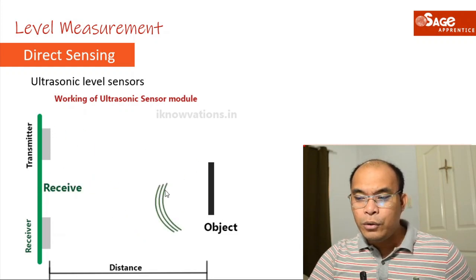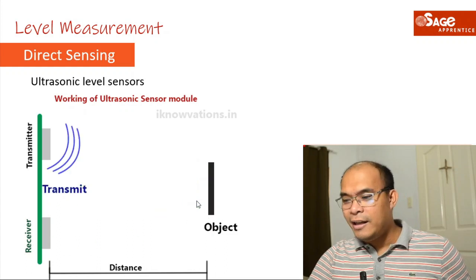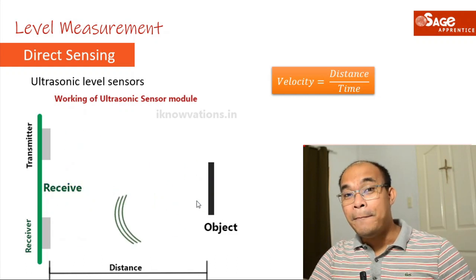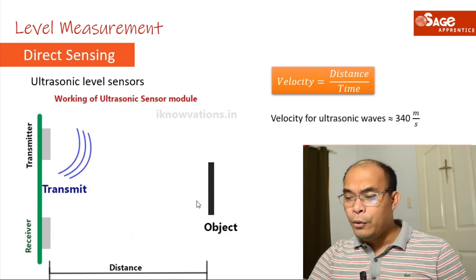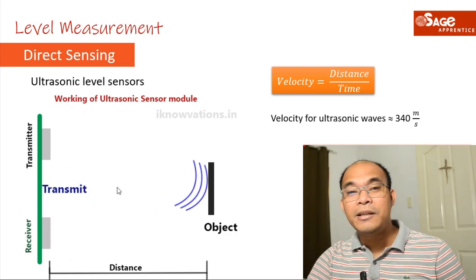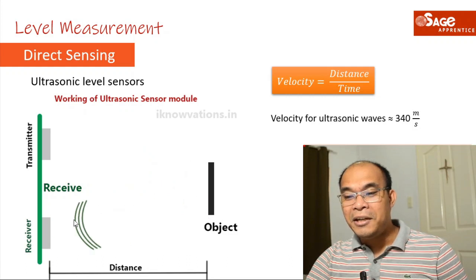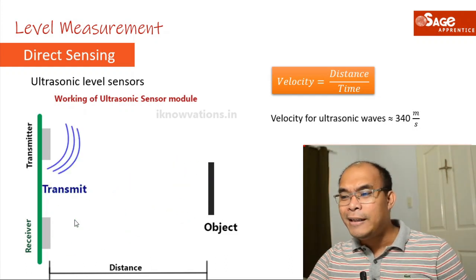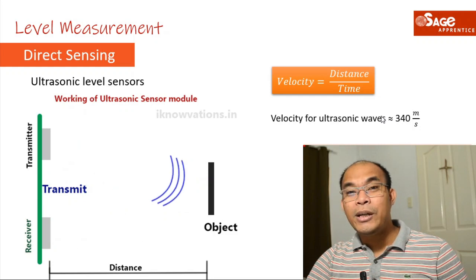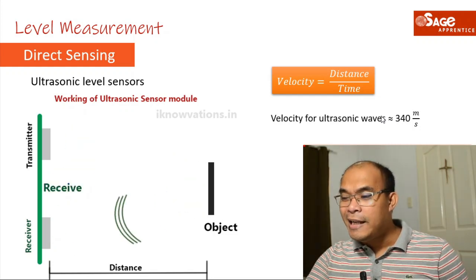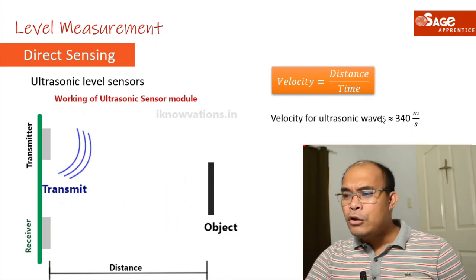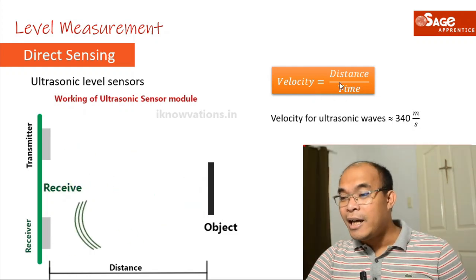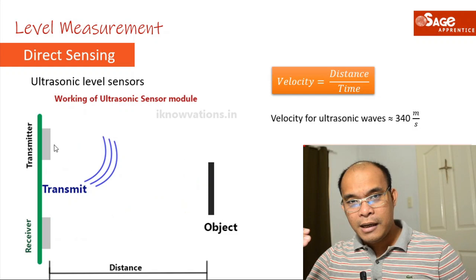To measure the level or distance from the sensor to the object, we use the physics concept: velocity equals distance over time. The velocity of ultrasonic sound waves is approximately 340 meters per second — this is a standard value that does not significantly change. Since the velocity is known, we can measure the time the signal takes to travel.